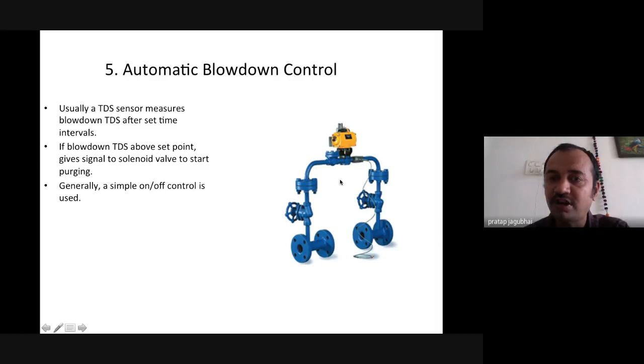If the TDS blowdown control is not available, the operator needs to give the blowdown manually, and in this scenario, he needs to always watch the steam pressure and whether the feed water pump is running. To avoid this, we need to have automatic blowdown control based on TDS, bottom blowdown TDS, and it will ensure that process pressure does not fluctuate. We maintain the TDS in the optimum limit so that we are not draining hot water from the blowdown pit, and we save heat by maintaining the blowdown TDS near the set point.